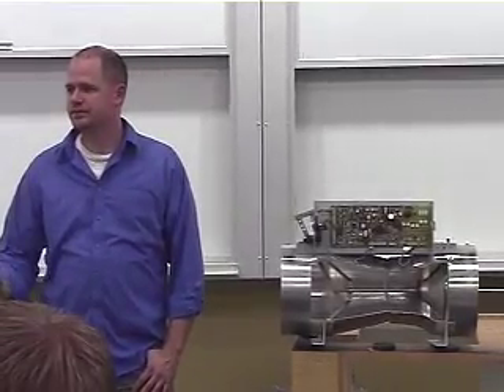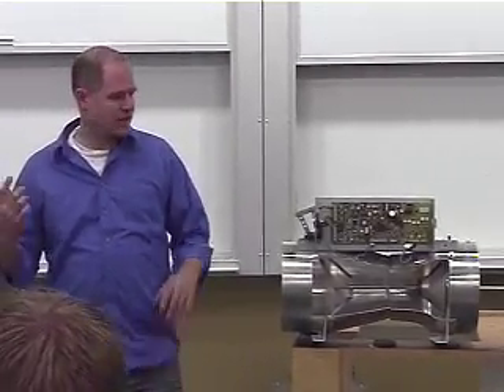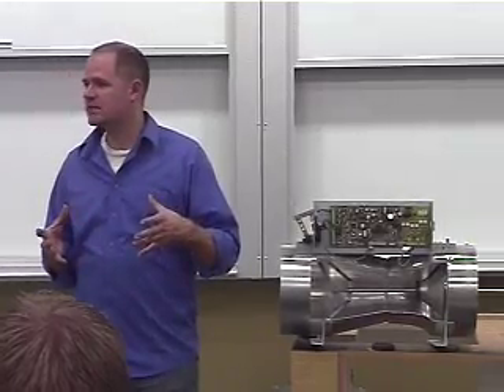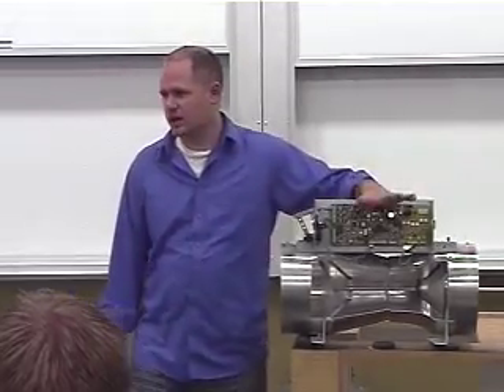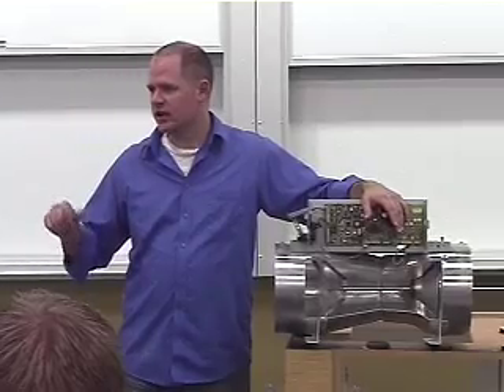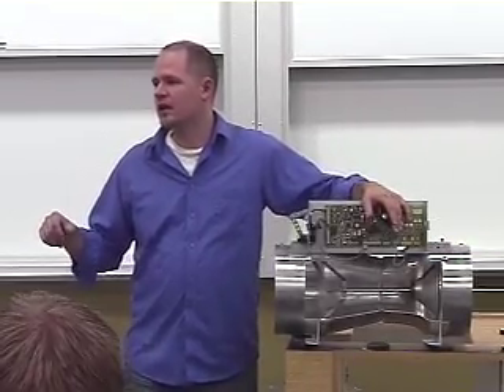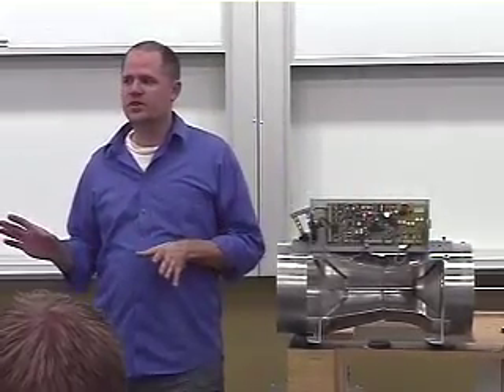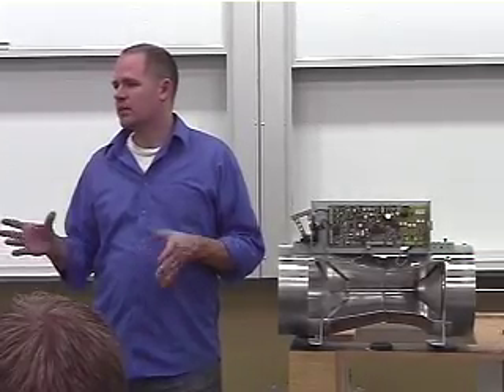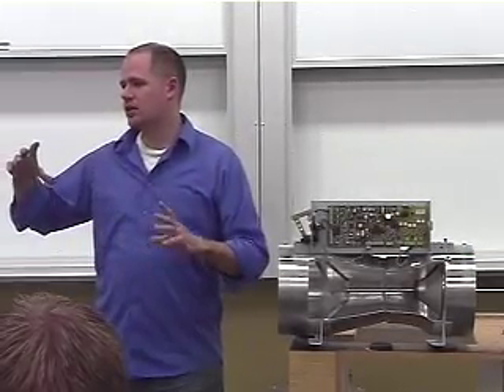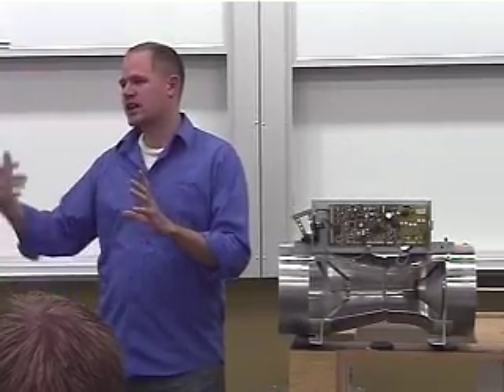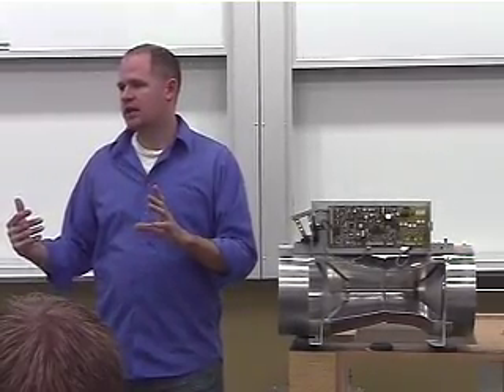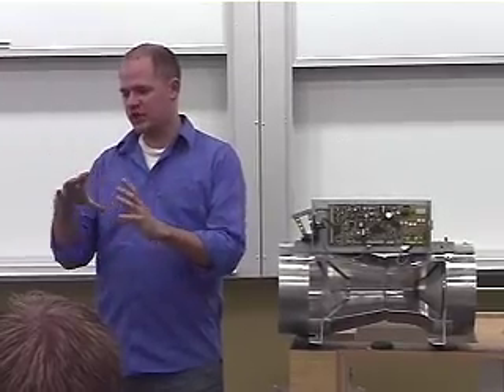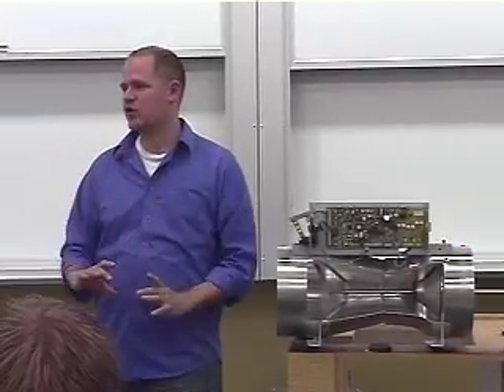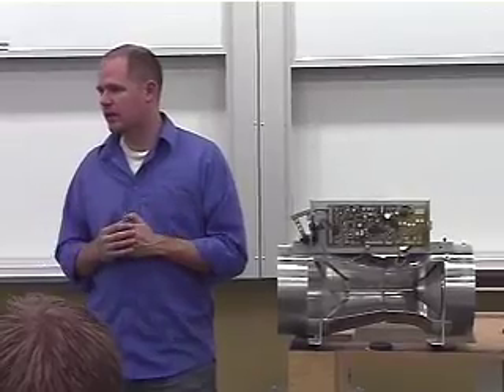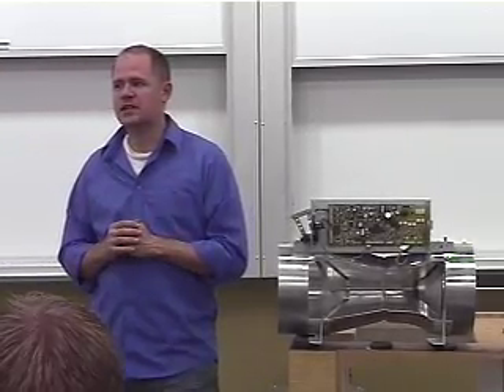Is the board fuse protected? They actually have circuit breakers on all of the transformers feeding these. So they're 100 VA circuits coming off of the transformers. There's little 100 VA circuit breakers on each transformer. I would have to look at the drawings to be sure which models they used. Typically, for a lab, I'll use the larger transformers that have individual circuit breakers next to it. They may have used the individual transformer and circuit breaker combo, so they have individual transformers per valve or whatever. But they are circuit breaker protected.